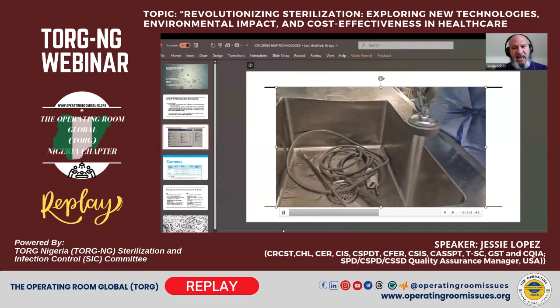So if our process has a manual cleaning, we use deionized water as our final rinse prior to automated processes. And the final rinse in the automated process is also with deionized water. You want to rinse this device for at least a minute. Again, this is to remove any minerals from the utility water and any microorganisms that were in that utility water off the surface of the device.